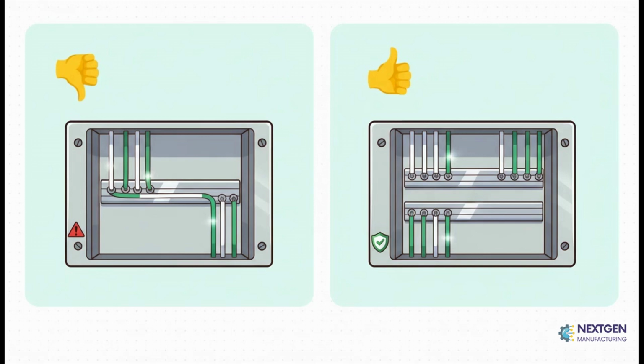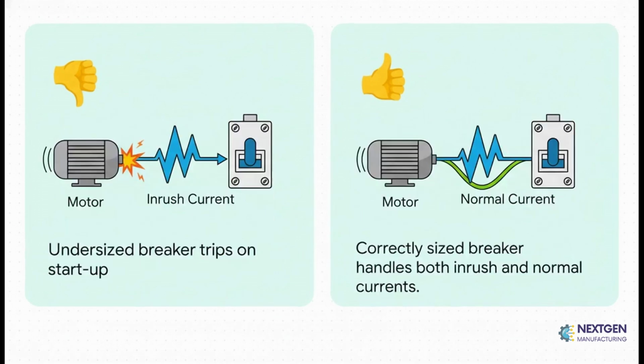The best practice is crystal clear: keep them separate. Another common equipment mistake has to do with overcurrent protection. Think about a motor at startup, it takes this huge gulp of energy, what we call inrush current, just to get going. It's way more than it needs to just keep running. So if you size a breaker only for the running current, you're going to have constant nuisance tripping. Proper load calculations have to account for both that initial surge and the normal operating load.